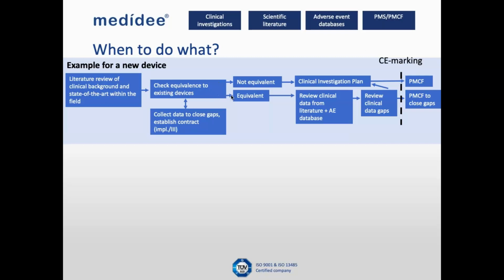On the other hand, if you can find equivalent devices, you can review the clinical data from the literature or the adverse event databases, and what you can source from that, those studies that are published there, you need to very thoroughly review those in order to determine if that is enough, if the level of evidence is enough to demonstrate safety and performance of your device, or if there are any major gaps in the clinical data. If there are any major gaps in clinical data, that could, for example, be very low quality of the papers, or only single-arm studies and no comparative studies, stuff like that, then you may end up with the conclusion that in order to close those gaps, you need to go back and do a clinical investigation before you have your CE marking.